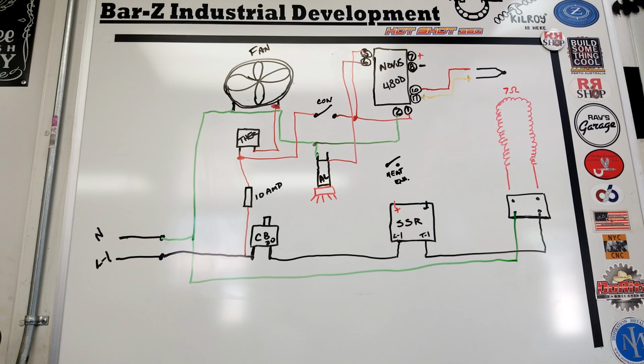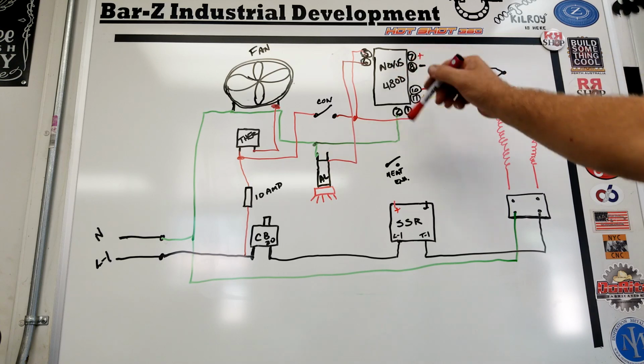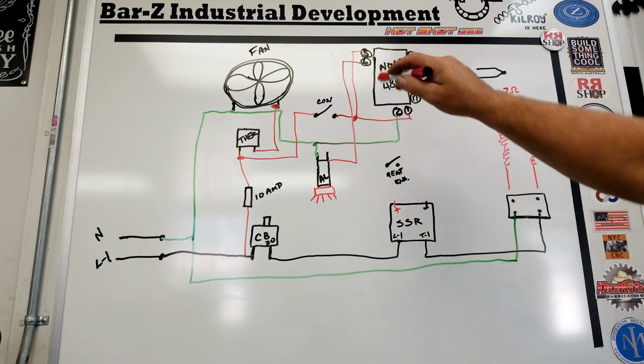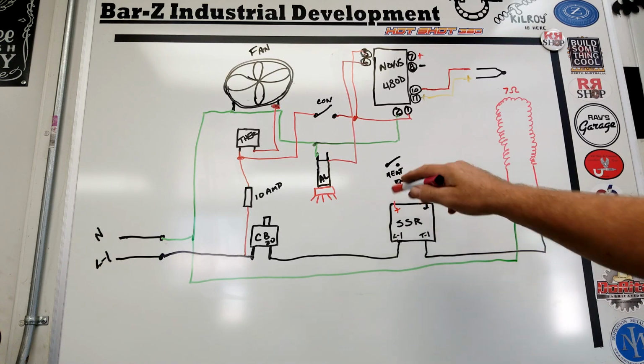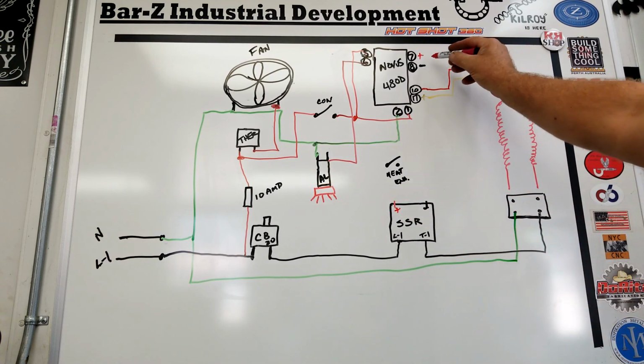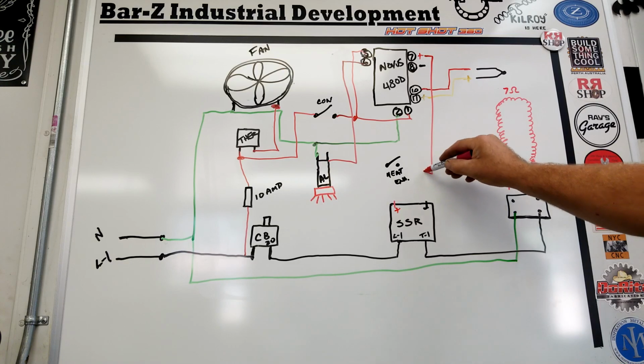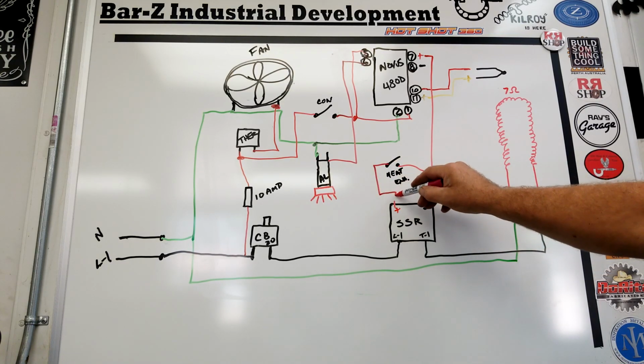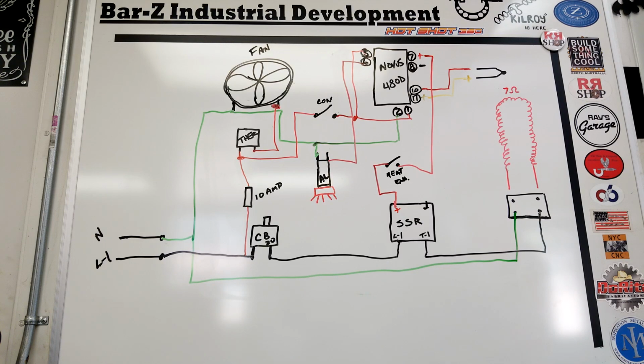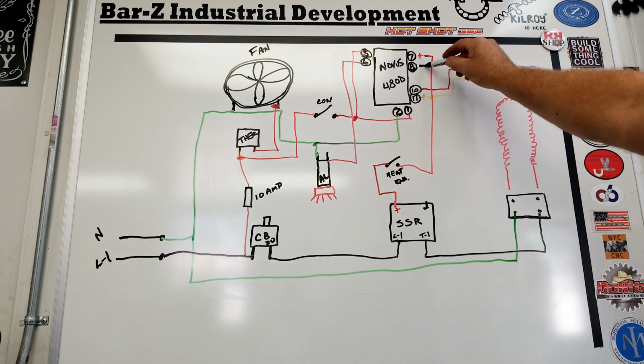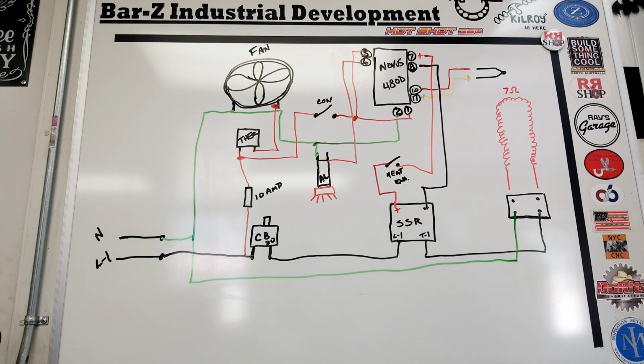Now I run this in a Belden cable. This is a low voltage DC, but I do run it between the Novus and the SSR through what I call a heat enable switch. So you can get this temperature controller up and running without triggering the SSR. Make sure your Novus is behaving properly, hit the heat enable, and then fire your SSR. So we got positive that comes down through this heat enable switch and then comes down to the SSR, and then negative, we just bring it out and come straight down, straight to the SSR. And you can use a 2-conductor Belden cable for that. Very low voltage, very low amperage.